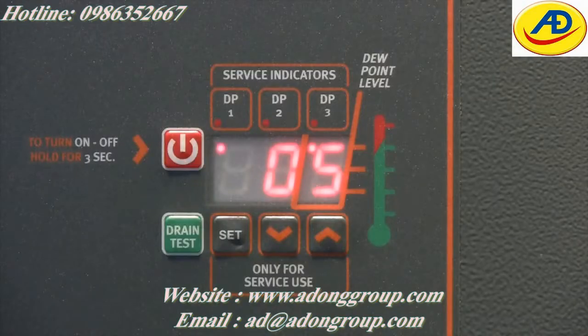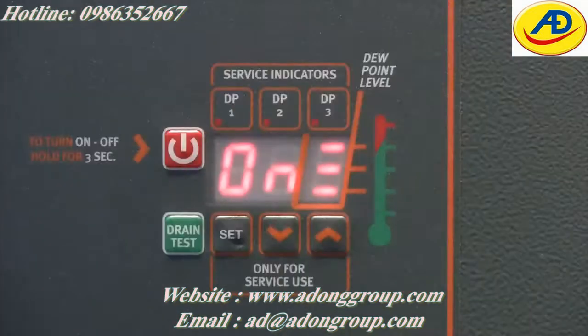The ProDry microprocessor control panel includes 5 keys and a 3-digit display with 3 signaling LEDs. The digital readout, which under normal operation indicates the dew point of the unit as well as fault codes. Dew point is displayed in numerical values, Celsius or Fahrenheit, or in graphical values, shown as bars.